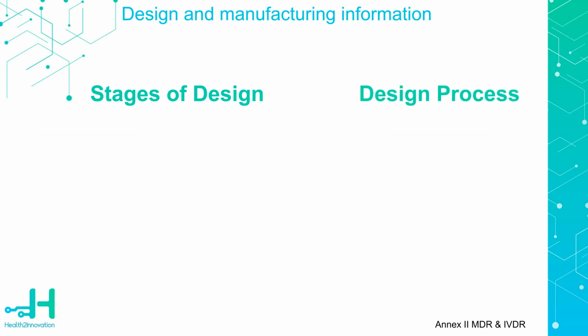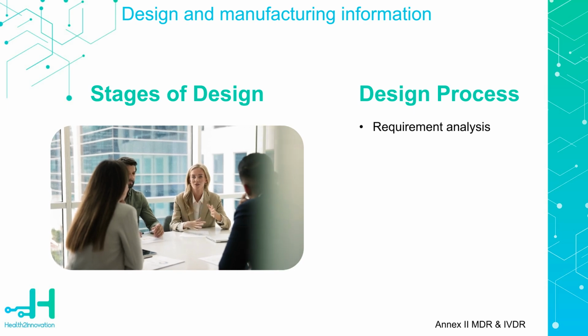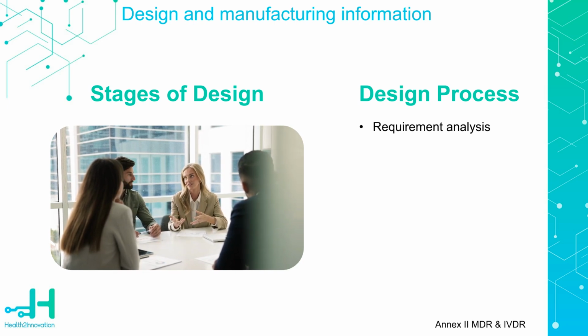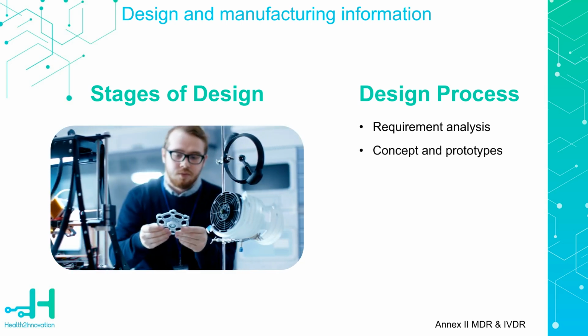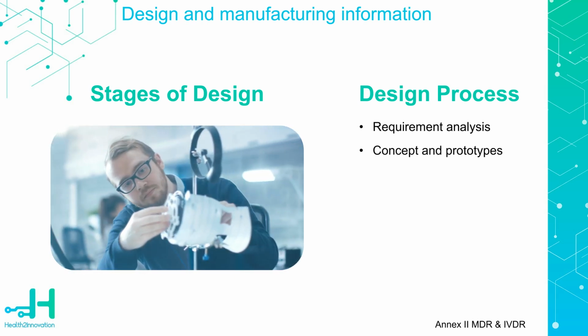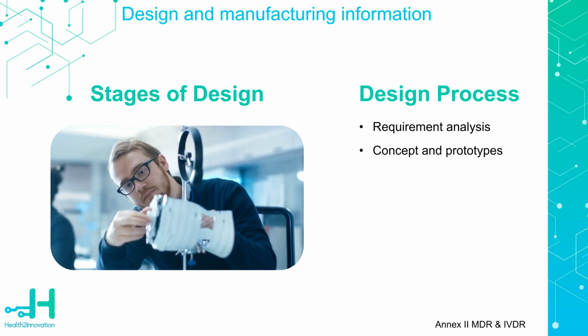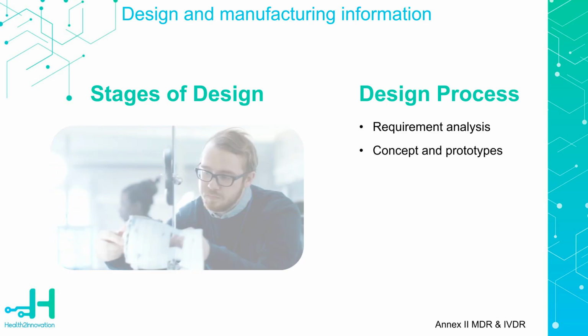To do this, detailed descriptions of each stage of the design process and the development methods used are documented and expressed using a risk-based approach. A thorough analysis on the design inputs and requirements that the device must fulfill should be done with key stakeholders and potential users. This could even include regulatory bodies. Based on these requirements, a concept design is evaluated, leading to a series of prototypes or mock-ups of the product. This allows designers to explore the user interface and make adjustments to the design before the technical specifications are written.